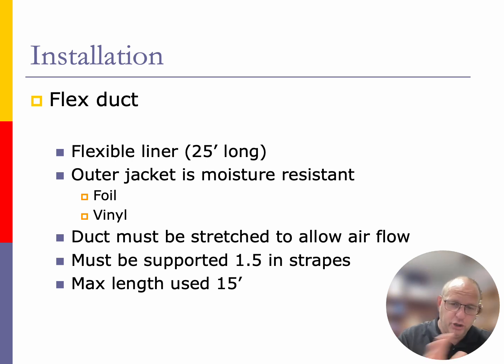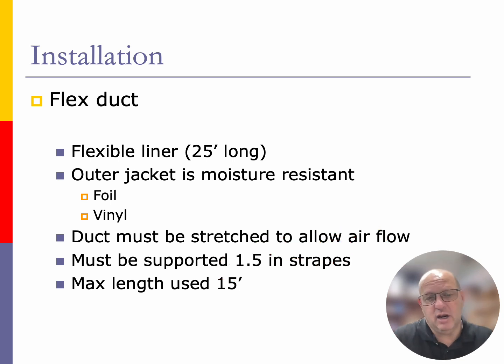In the book and on your test questions, it's going to ask you, how do you support this? It needs to be supported every 4 feet, and it needs to be supported with a 1.5 inch strap that's on that ductwork. So there's your answers to your questions for your homework. 1.5 inches strap, but also it's going to be supported every 4 feet. Maximum length, residential, 15 feet, no more. Get that round pipe as close as you can to that boot. And then if you need to, run your flexible duct to the actual boot. And then no more than 15 feet for residential.